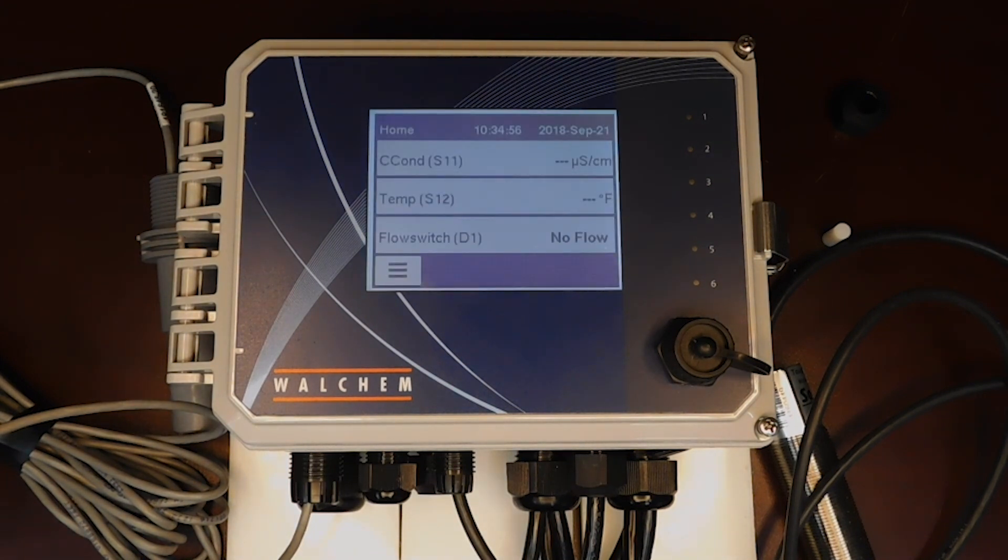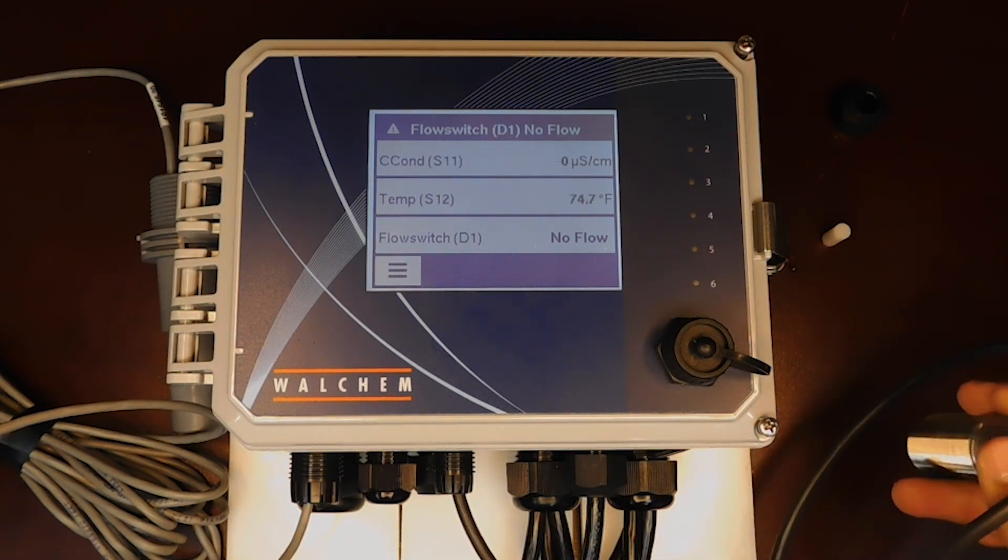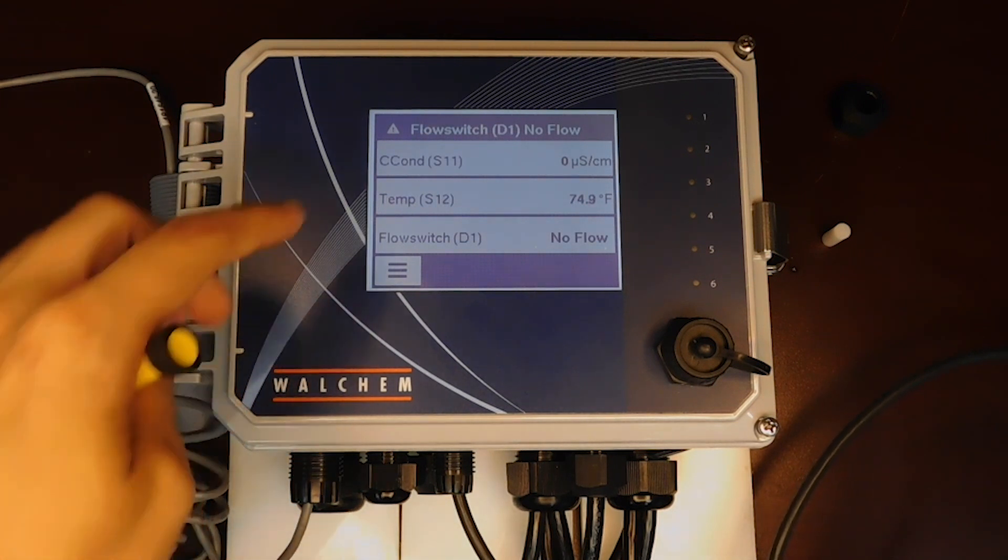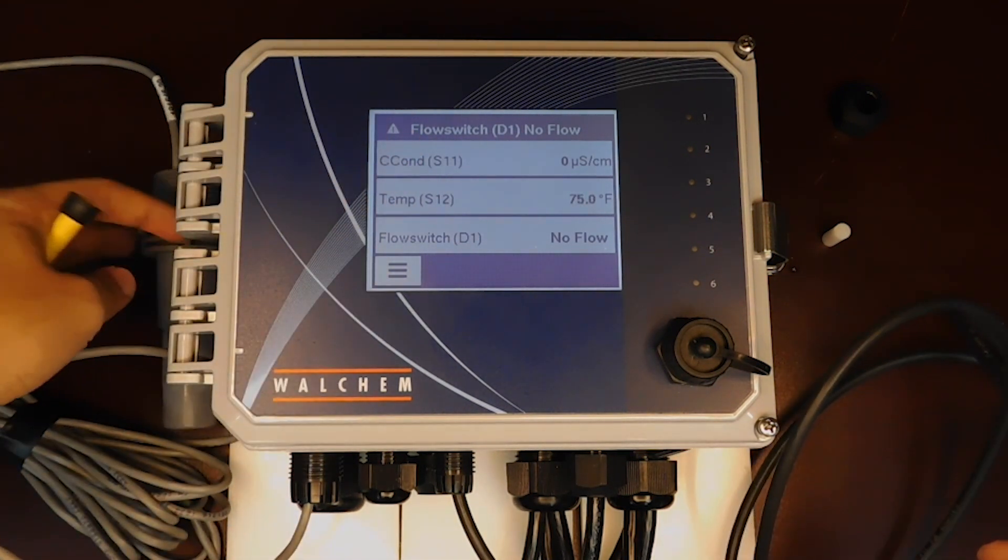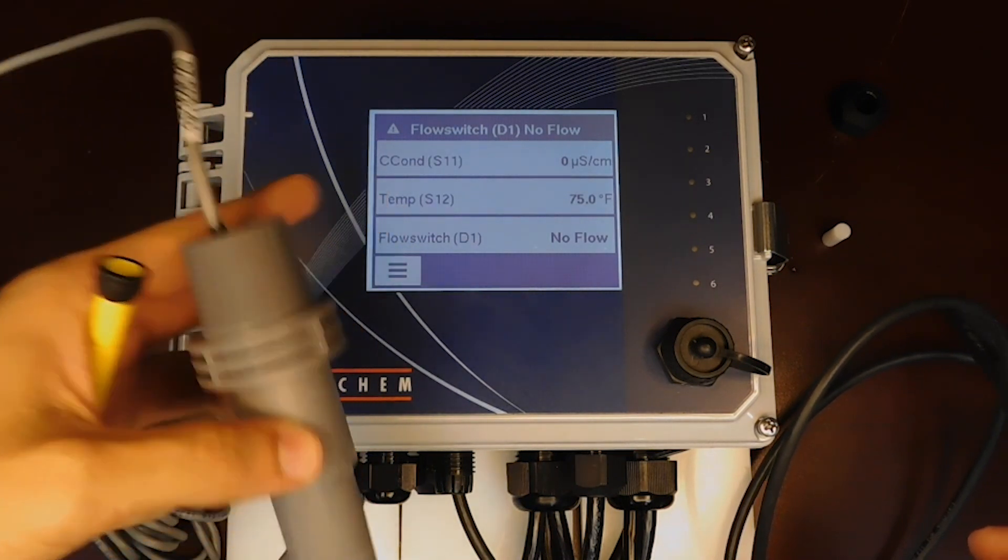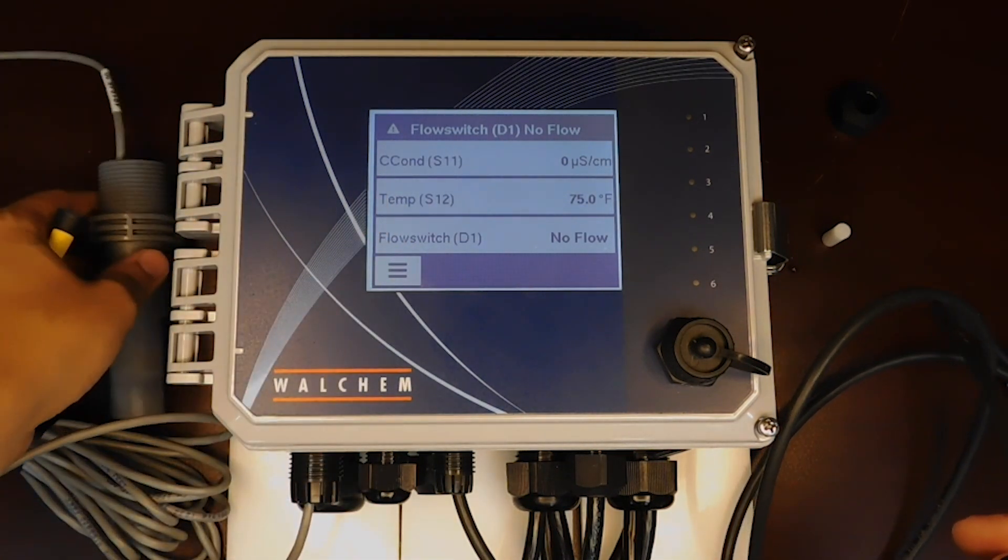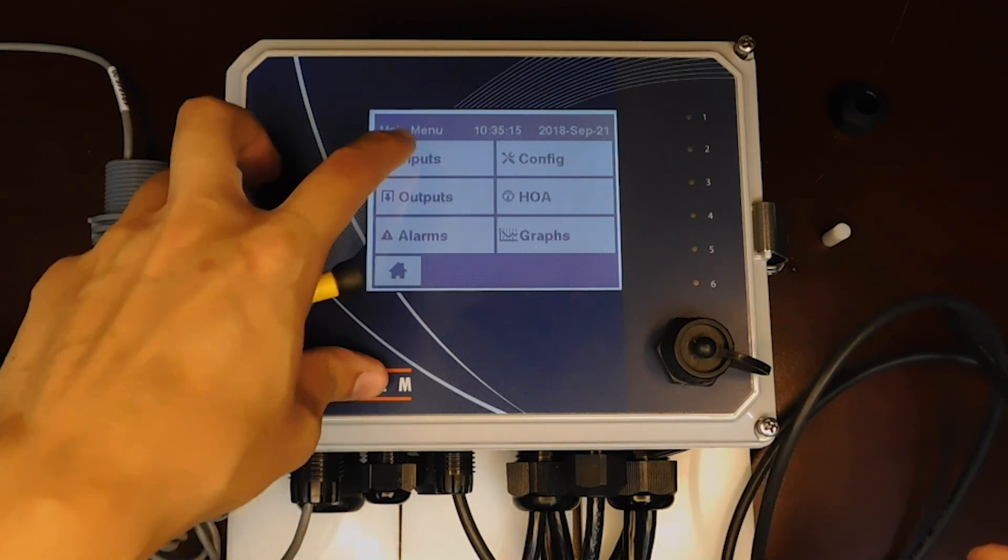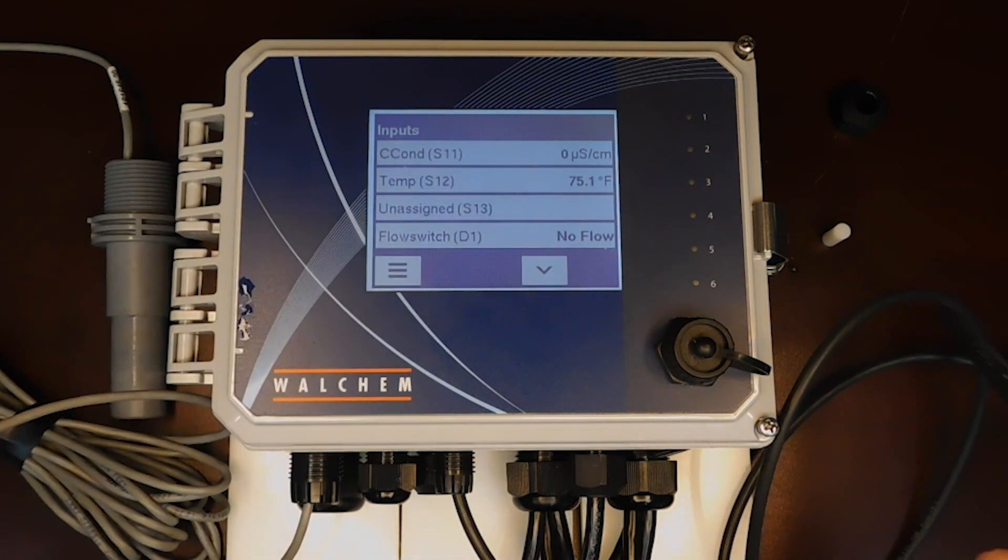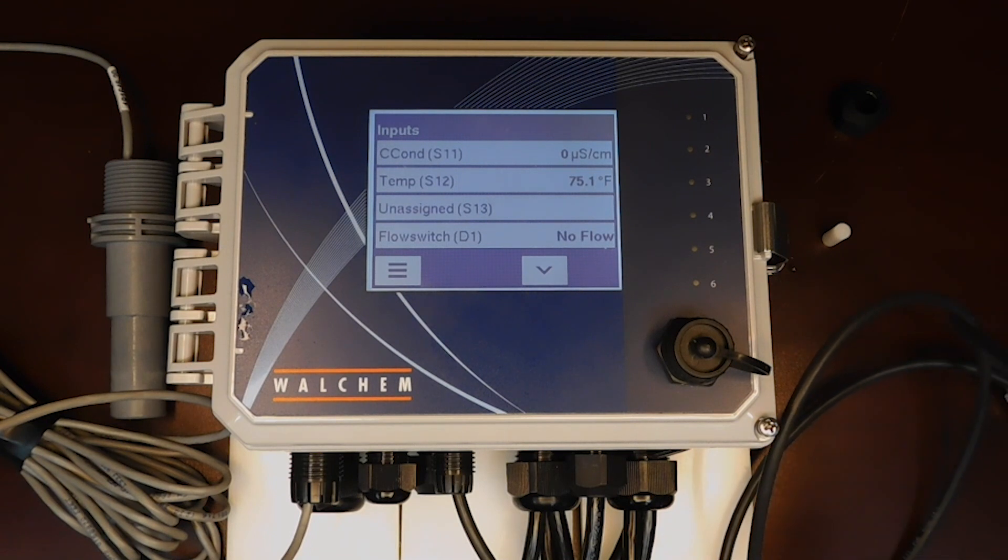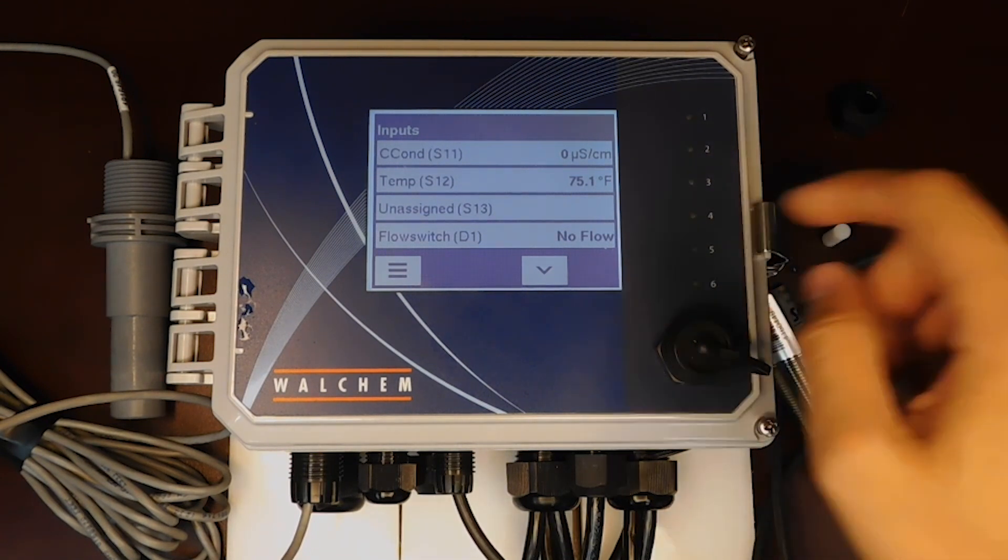Now that the controller is booted up, we're going to need to go to the inputs in order to program this sensor. You can see here S11 is the conductivity sensor, S12 is the temperature element in this conductivity sensor. We're going to go to inputs, go to unassigned S13. That's the four to 20 milliamp input that we just wired the sensor into.